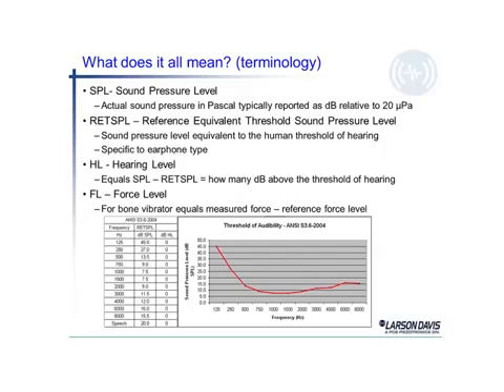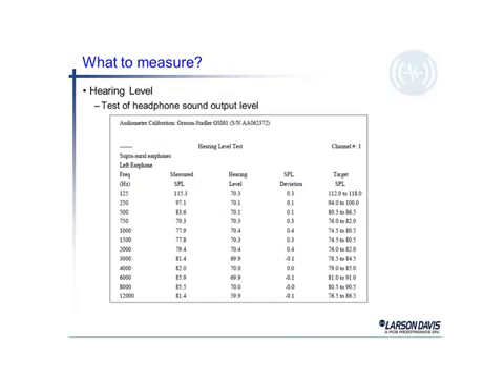The audiologists are typically talking in hearing level, or HL. So as you spin the dials and work with the audiometer, it's going to call out a level in dBHL. If we're working with the little bone vibrator and putting a signal into the bone, they talk in units of force level, or FL. So that's how an audiologist works. What to measure? Hearing level is a typical test that is done for an audiometer to see how it's performing.